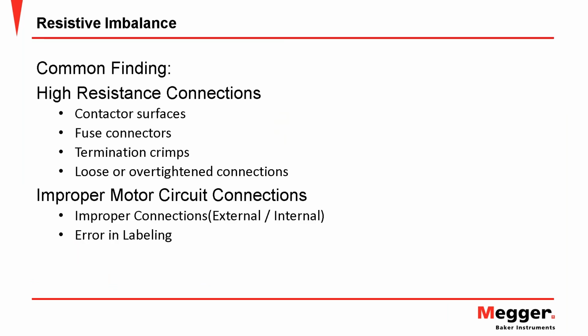So here's some cases, and again, reiterating some of the value of each of these tests. So going back to low voltage, again, I mentioned earlier, we're typically looking for imbalance in the circuit, and those imbalances are caused by high resistance connections. Most often, probably the most often found problem with resistive imbalance and high resistance connections is in the terminations of the motor in the junction box, termination crimps. But it could be contactor surfaces that have been pitted over time.